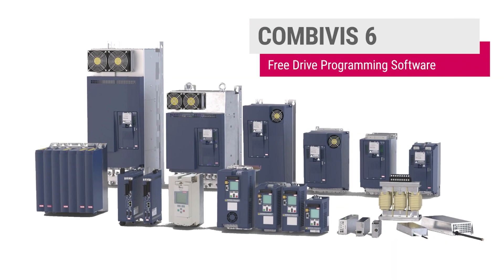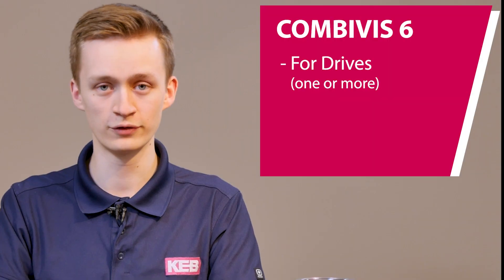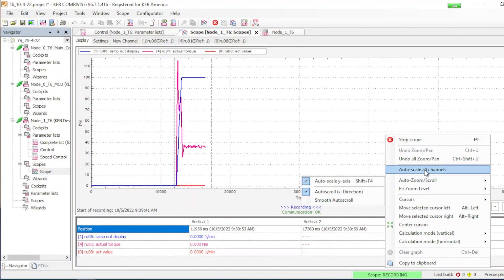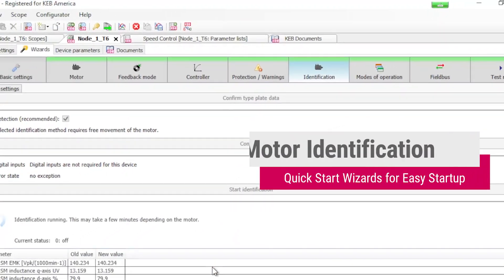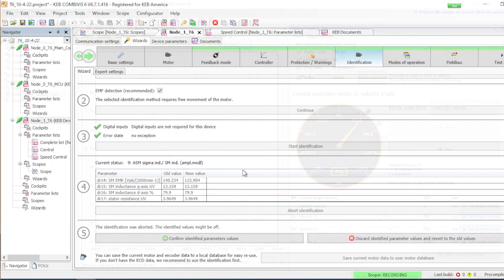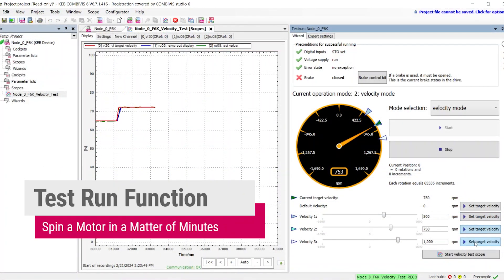Let's talk specifically about CombiVis 6. If you're only working with drives, CombiVis 6 will be all you need to connect to one or multiple drives for parameter adjustment, doing a motor setup through the wizards, or to use the 16-channel scope to track any relevant parameters over time for any testing. CombiVis 6 has a motor identification setup under the wizards for easy tuning, as well as the test run feature with all the relevant information in front of you.